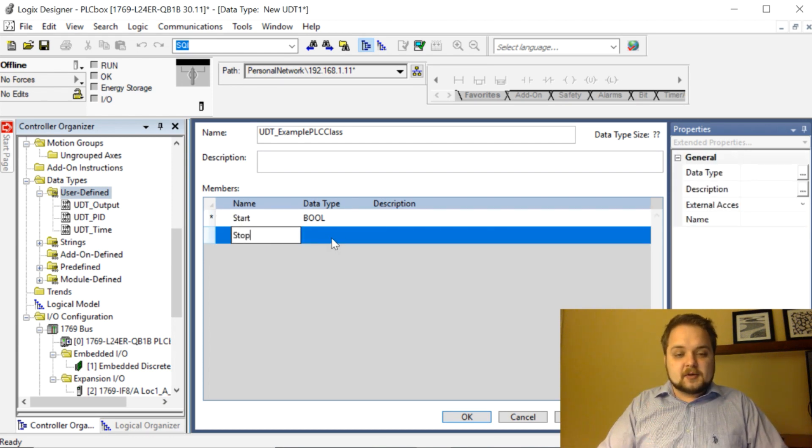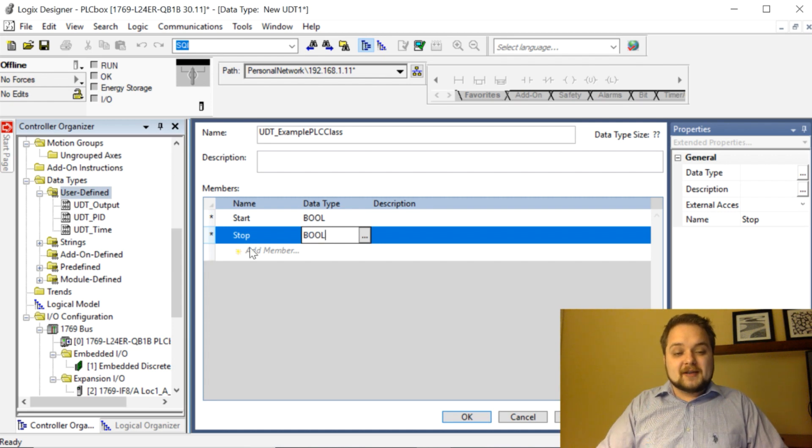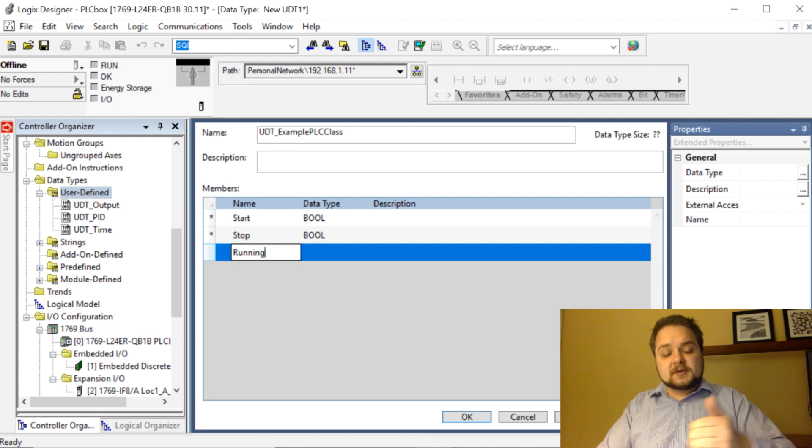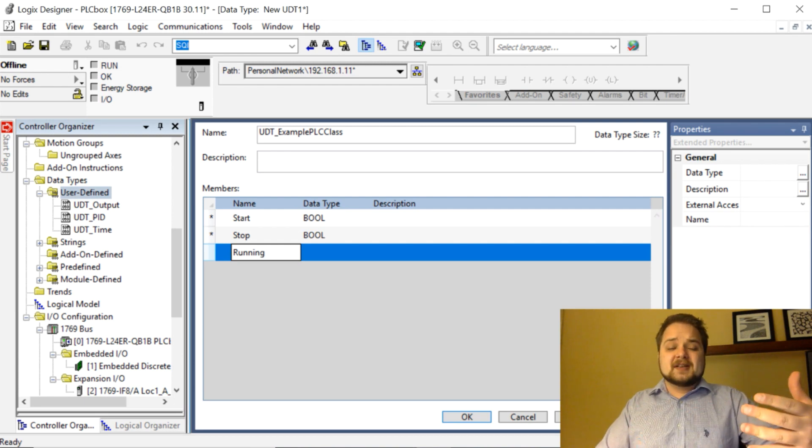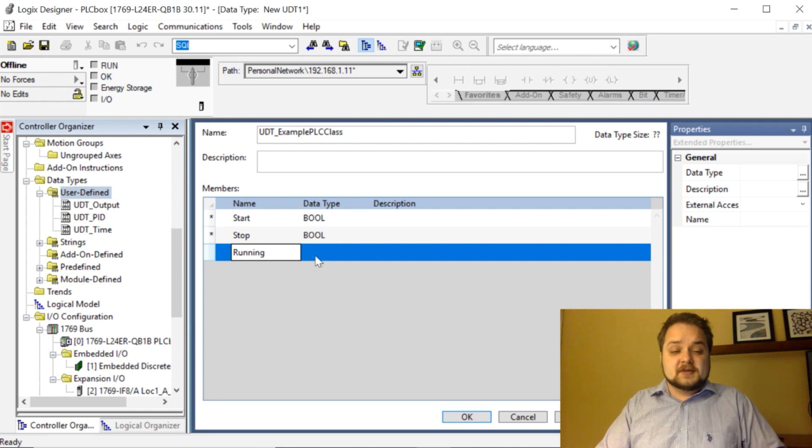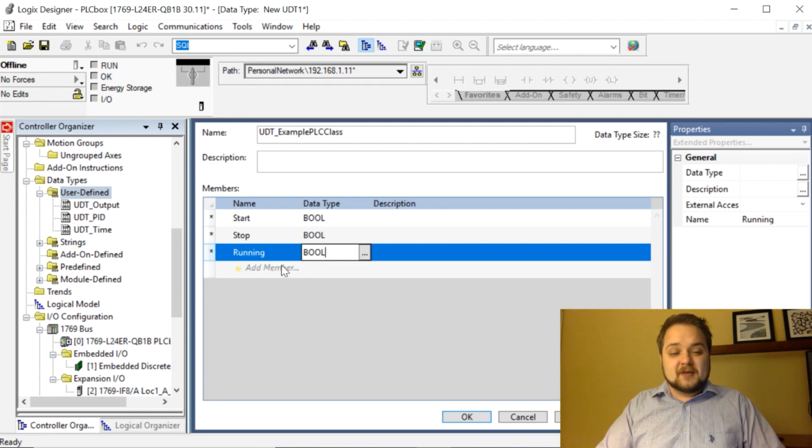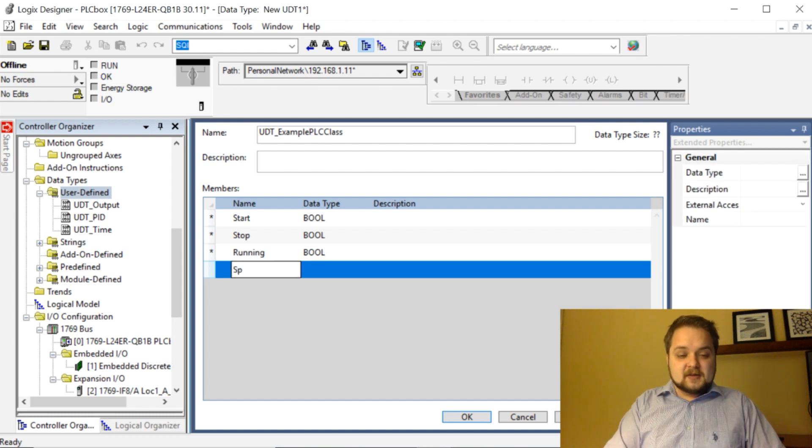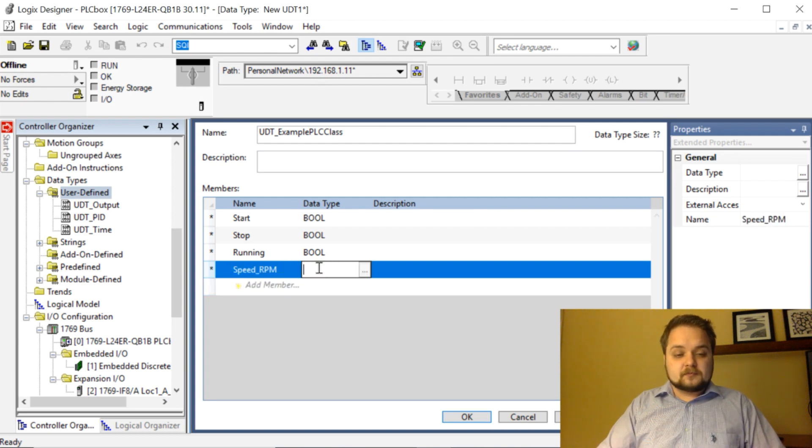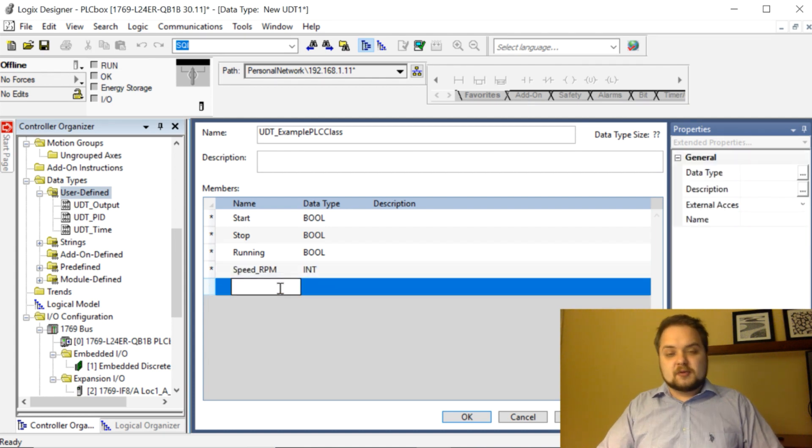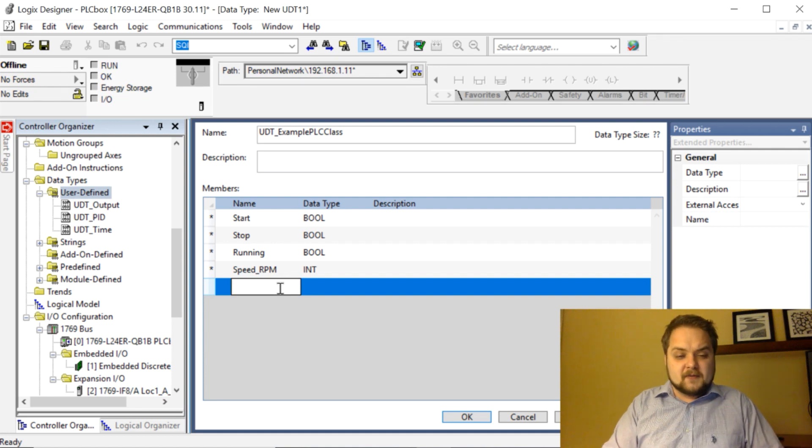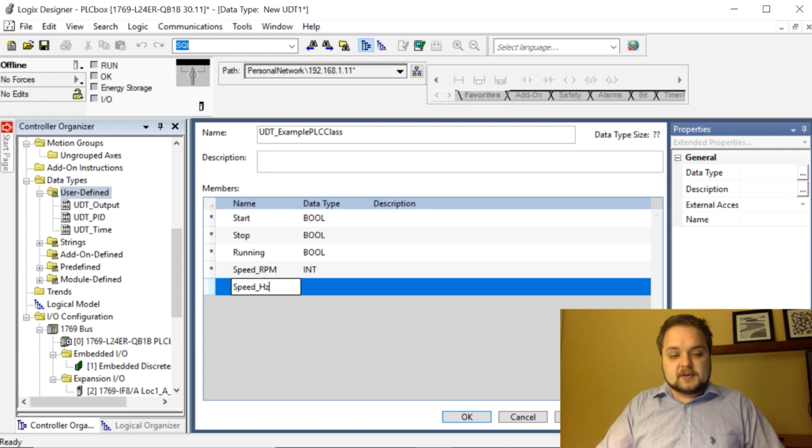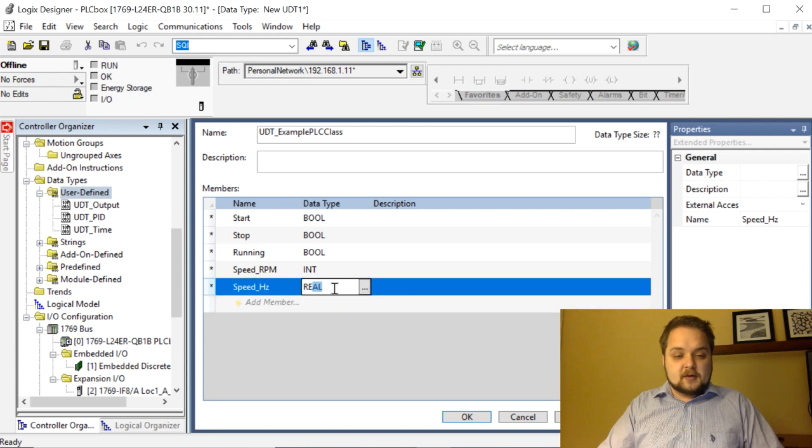Stop is also going to be a boolean. We're going to have a confirmation of the motor actually running, and these names essentially become tags within our UDT structure. Boolean running is going to be our feedback. The motor is also going to have a speed reference in RPM. In RPM this is going to be, instead of making a real, we'll make it an integer assuming that there's going to be no 2000.01 RPM for example. We're also going to have a speed in hertz, and hertz is going to be a real value.